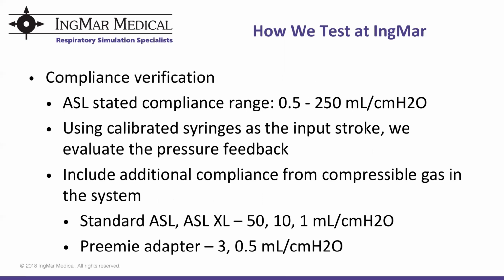The next test we perform is called compliance verification. The ASL operating range of compliance is 0.5 to 250 milliliters per centimeter of water. Using the same calibration syringes we use for the volume verification, we evaluate the pressure feedback and use this to determine the compliance. Please note that the compressible gas that's inside the cylinder or the lung is also considered in this evaluation. The values that are measured for the standard and XL ASL are shown below, which is 50, 10, and 1 milliliter per centimeter of water. In the preemie adapter, we measure from 3 down to 0.5 milliliters per centimeter of water.